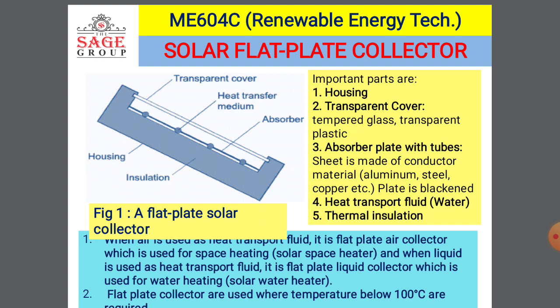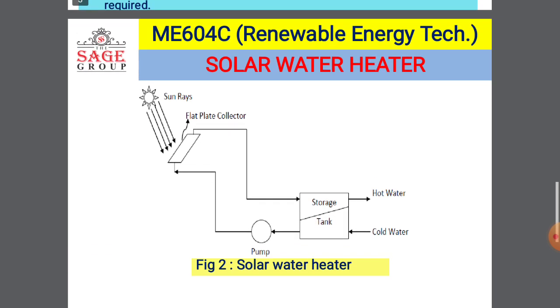When this solar flat plate collector is exposed to the sun for a long time, there are chances of overheating of the whole device and chances of heat leakage to the surroundings. So in order to reduce that, thermal insulation is also provided. According to the fluid being circulated through the tubes, these solar flat plate collectors can be a water or liquid flat plate collector, or an air flat plate collector. Flat plate collectors are generally used when a temperature below 100 degrees Celsius is to be obtained, meaning the temperature rise in the fluid circulated through the tubes is around 100 degrees centigrade.